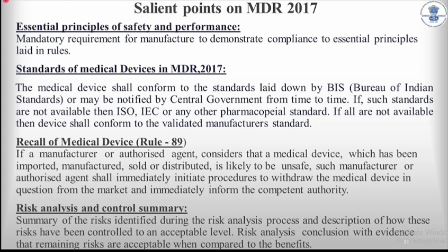One of such events is called the essential principles of safety and performance. It's mandatory for every manufacturer or importer to demonstrate their compliance with the essential principles in medical device rules.